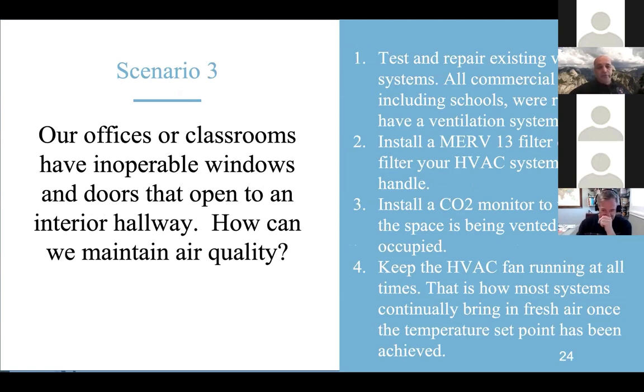You're in an office or classroom with no operable windows or doors, or the doors open to the hallway. How can you maintain good air quality when you can't open a window or door? Same as the first scenario: test your ventilation system, make sure it's operating and the required amount of fresh air is coming into the space. You've added the MERV 13 filter, you have CO2 monitoring, and you're keeping the fan running. It's one of the best ways to deal with those spaces.